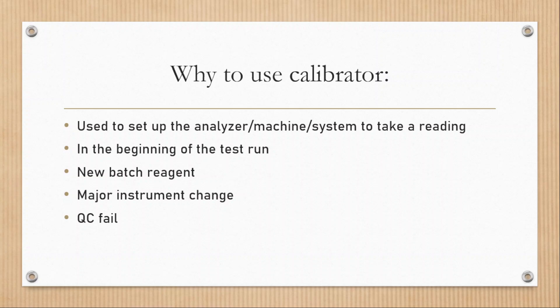When we use new batch of reagent, we need to calibrate. In case of major instrument part or system change, recalibration is needed. Also, when quality control fails, calibration is required.